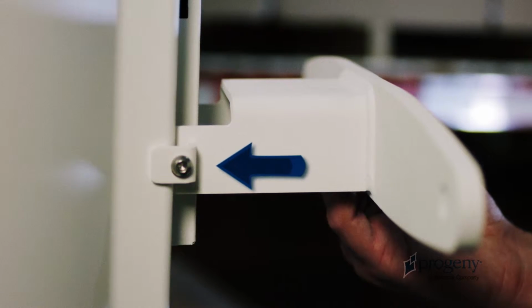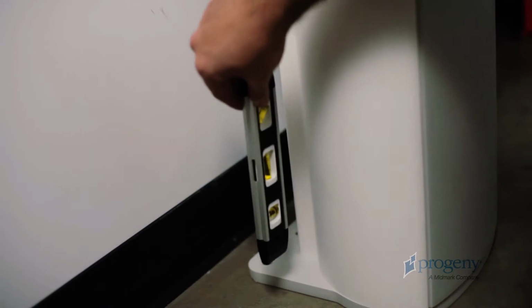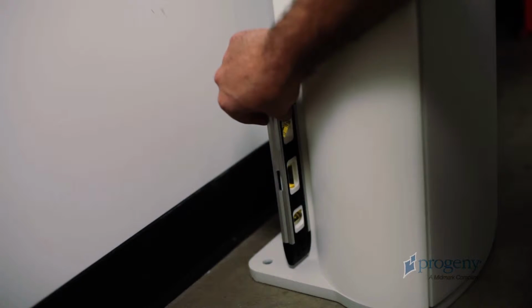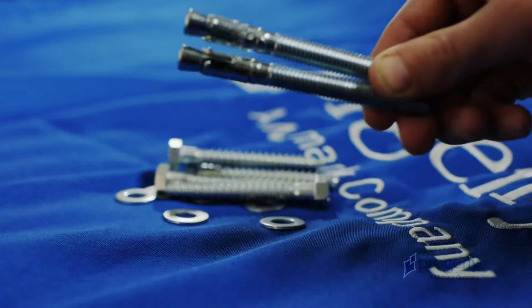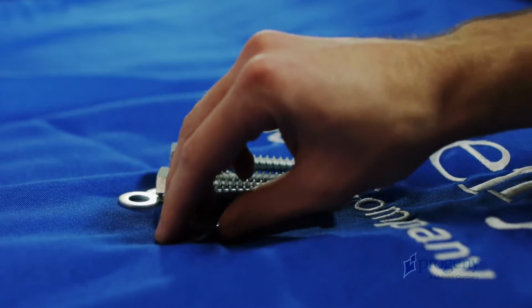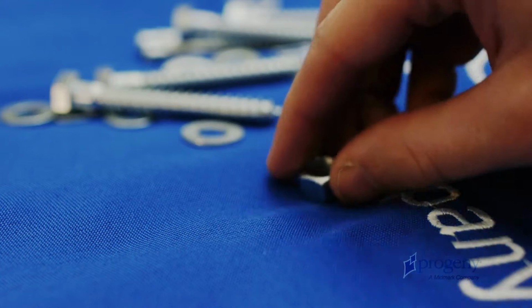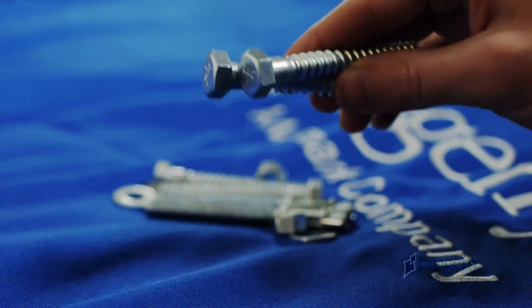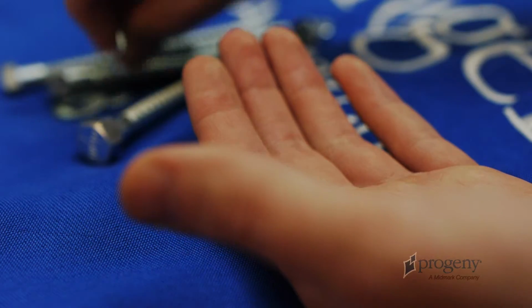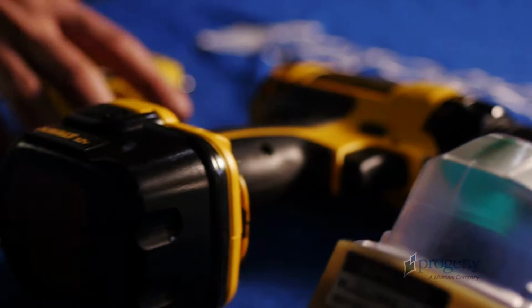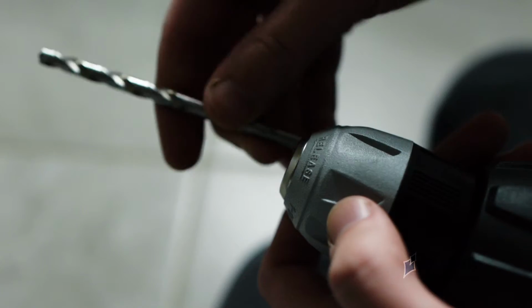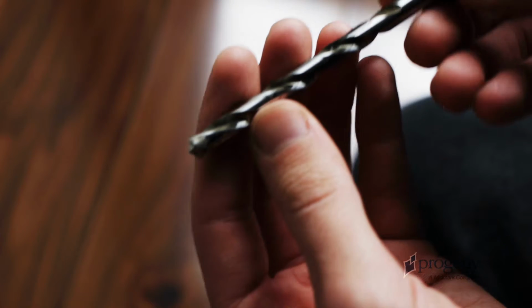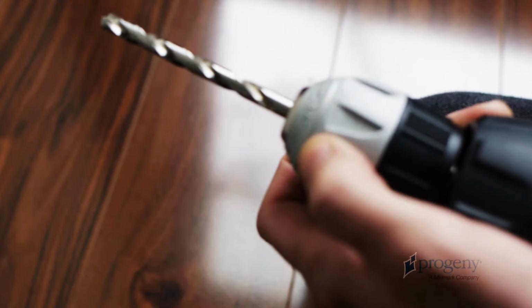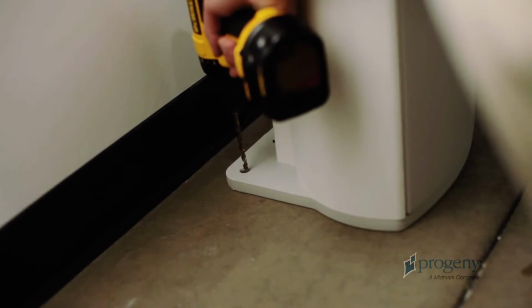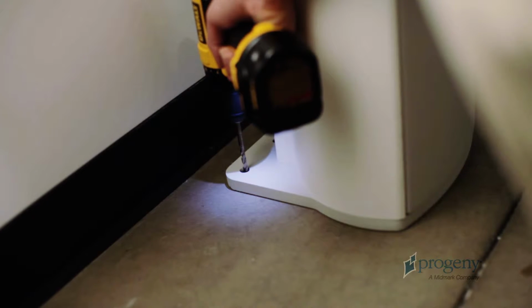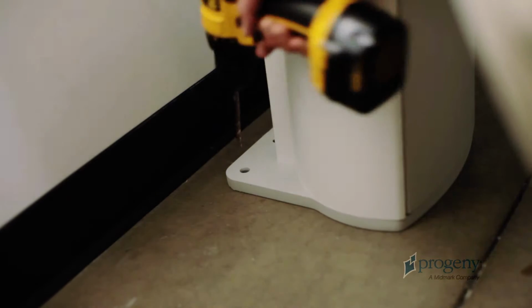You must attach the clamps, but do not completely tighten until checking to make sure that the main column is level. Select 2 cement anchors, 2 washers, and 2 nuts from the hardware kit. For wood floors, select 2 lag bolts and 2 washers. For cement or tile floors, use a 3/8 inch drill bit. For wood floors, use a 1/4 inch drill bit. Insert anchors and tighten with a 14mm socket wrench.